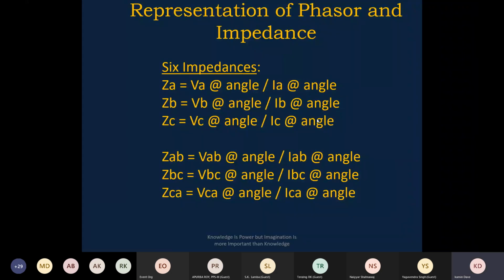So they normally keep it for backup coverage. Only the phase to phase or three phase fault is required to be detected, not phase to ground. Again, the phase to ground current is very small, like 14 ampere or 10 ampere, because it is restricted by the NGT through the NGR. So anyhow, it will not be detected by this relay. So only the phase to phase loop or three phase loop has to be detected. But 30-degree compensation is required, because there is a delta star YD11 transformer. So the YD11 30-degree difference has to be compensated.